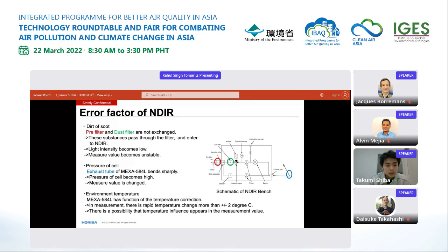The third is environmental temperature. The Mexa 584L is equipped with a temperature sensor and performs temperature compensation. However, sudden changes in temperature during the measurement can affect the reading. There are several other error factors, so the measuring equipment also requires maintenance.